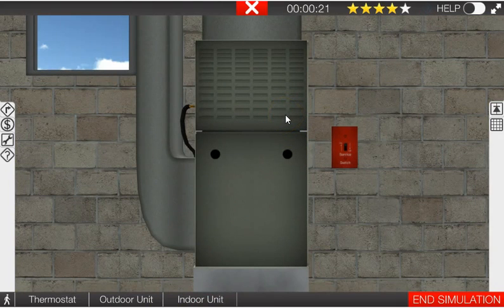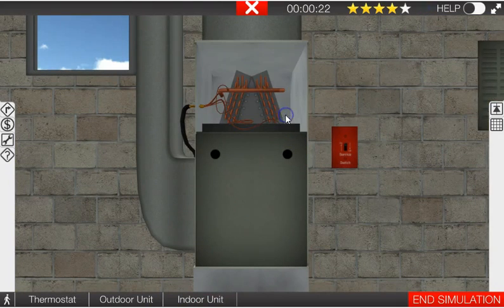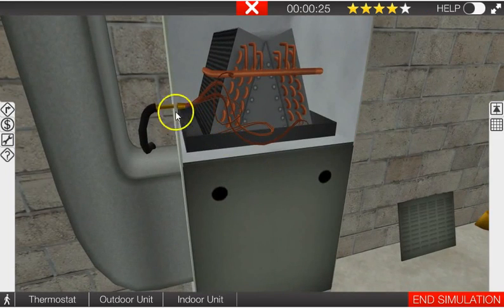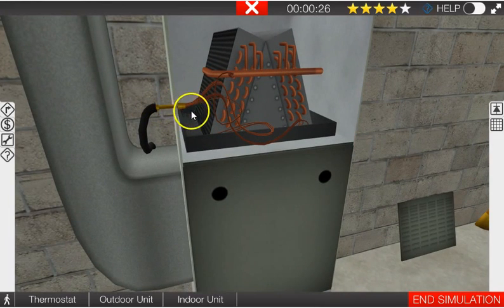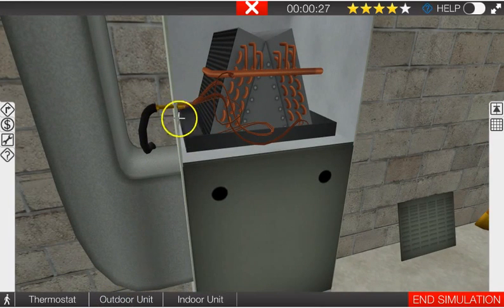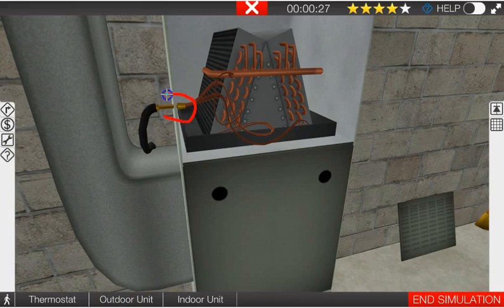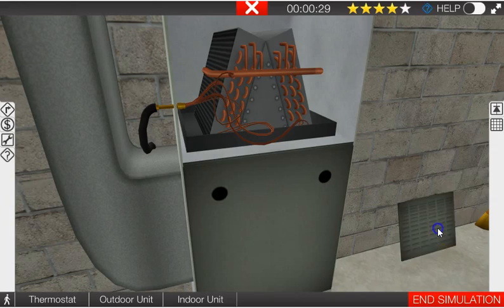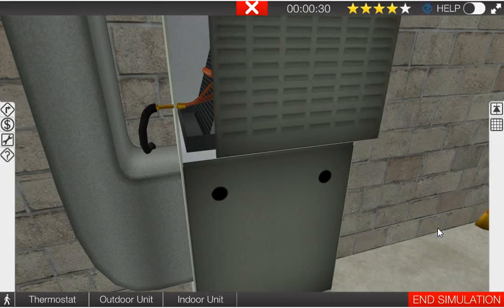And see what kind of metering device we have. We have a fixed orifice system here, we don't have a TXV. So that's one thing that you're going to need to check before you do any system pressure measurements.